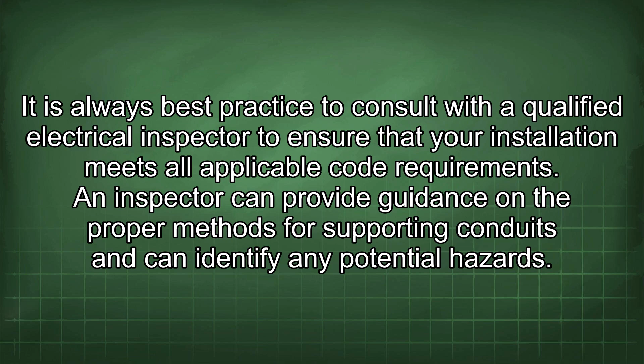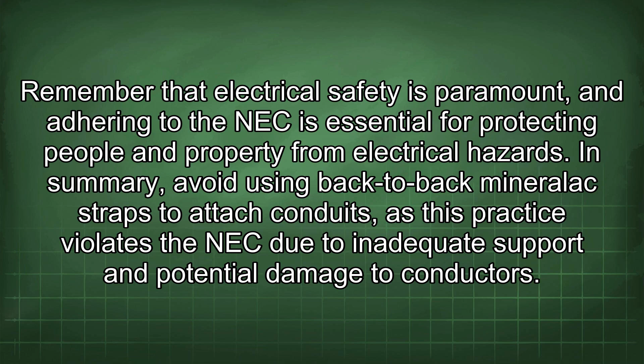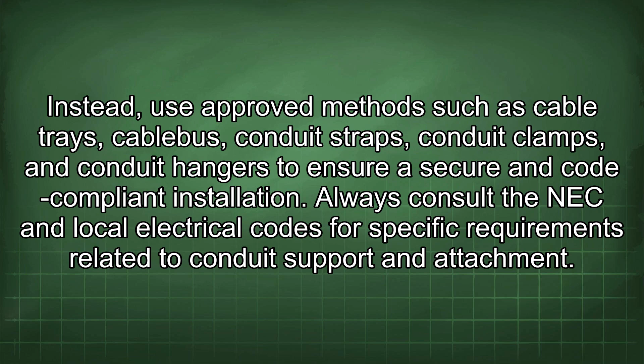In summary, avoid using back-to-back mineralac straps to attach conduits, as this practice violates the NEC due to inadequate support and potential damage to conductors. Instead, use approved methods such as cable trays, cable bus, conduit straps, conduit clamps, and conduit hangers to ensure a secure and code-compliant installation. Always consult the NEC and local electrical codes for specific requirements related to conduit support and attachment.